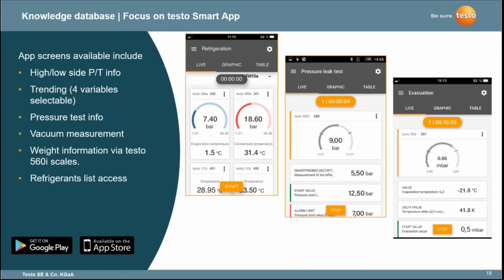And the smart app has various screens depending on your use. If you've got it connected to the manifold and it's in second screen mode, whenever you change the measurement mode on the manifold, it will automatically reflect that within the app because the manifold is always the master device. But you've got screens for your traditional manifold view, high side and low side.